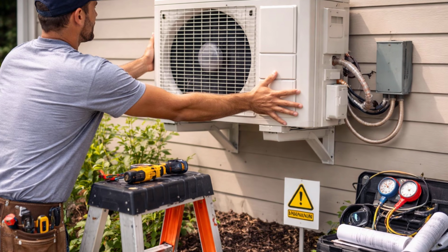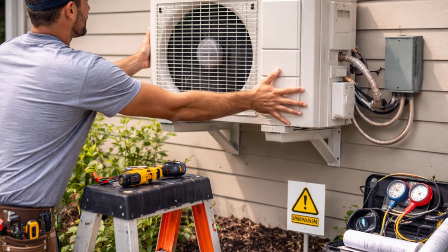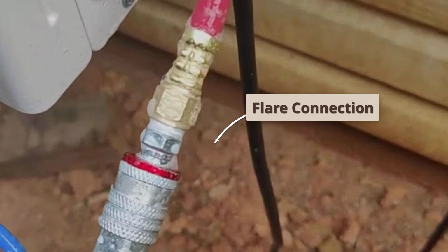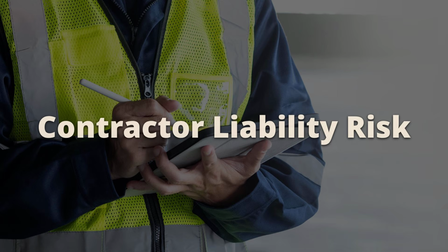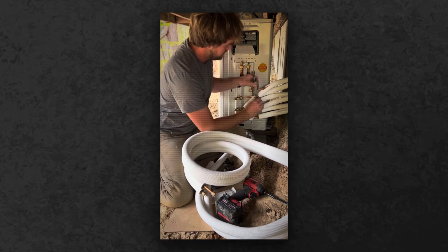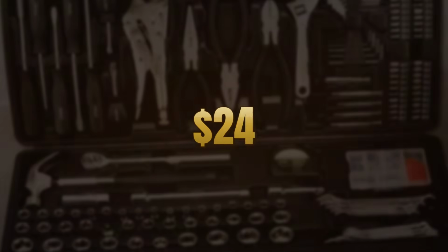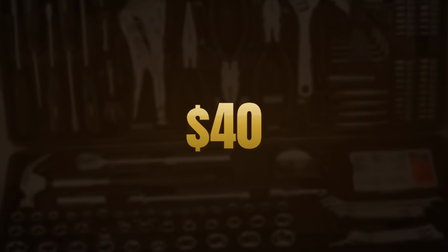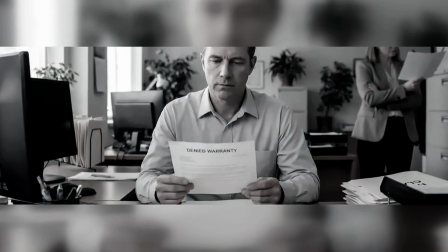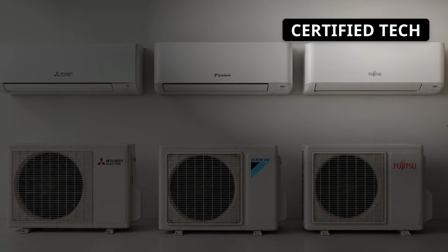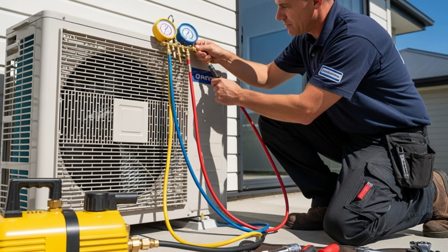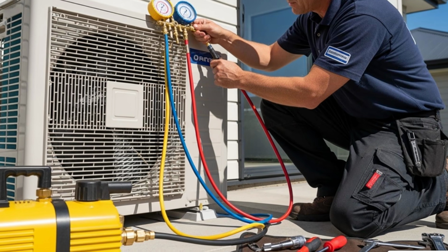When that happens, no licensed HVAC contractor wants to inherit the system. They did not install it. They cannot verify the integrity of the line set. They are not putting their professional license and their insurance on the line to troubleshoot someone else's flare job done with a YouTube tutorial and a $40 Harbor Freight toolkit. You are left with a dead unit on the wall and a manufacturer warranty that explicitly requires professional installation to be valid, professional installation that you never had. Licensed technicians install Mitsubishi, Daikin, or Fujitsu mini splits in their own homes because those manufacturers require certified dealer installation, which means the refrigerant circuits are done correctly from day one.